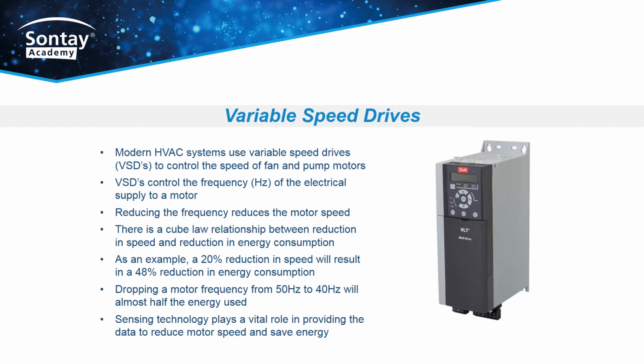There is a cube law relationship between reduction in speed and reduction in energy consumption. As an example, a 20% reduction in speed will result in a 48% reduction in energy consumption. Dropping a motor frequency from 50 Hz to 40 Hz will almost halve the energy used. Sensing technology plays a vital role in providing the data to reduce motor speed and save energy.